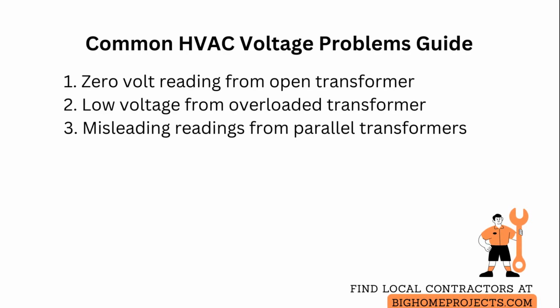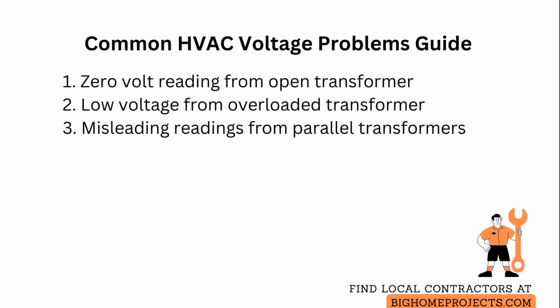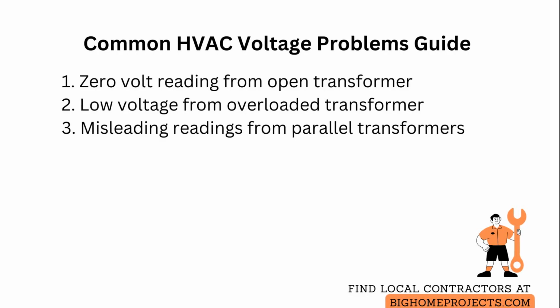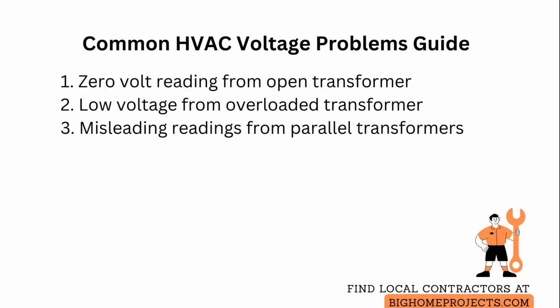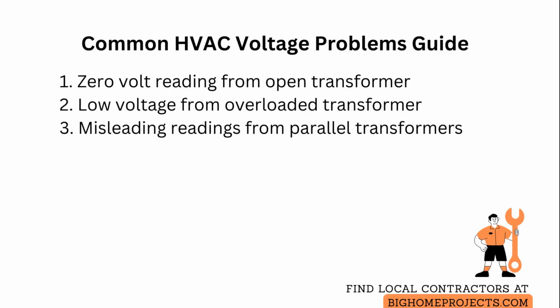appropriate secondary voltage and amperage ratings, and misleading readings from parallel electronics or backfed circuits when multiple transformers are present, which is corrected by isolating each transformer secondary, using diode isolation or a single centralized transformer to prevent circulating currents and ensure accurate measurements.